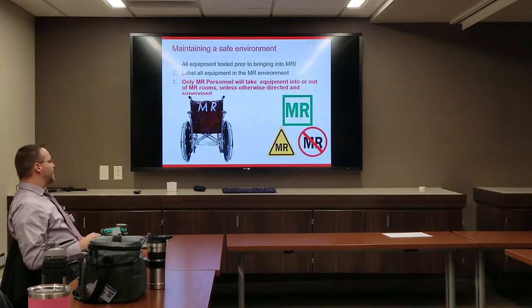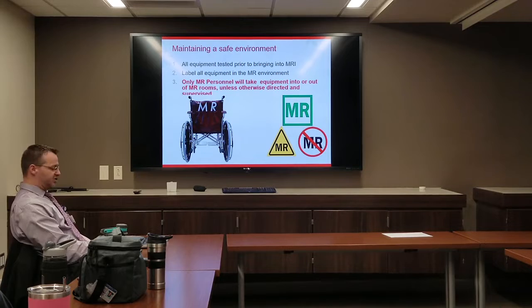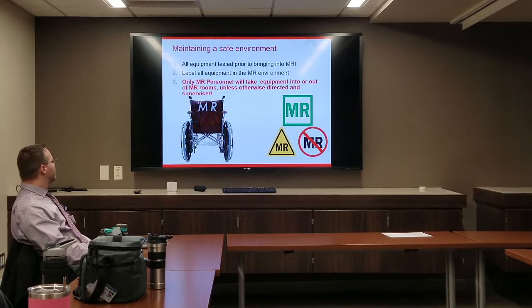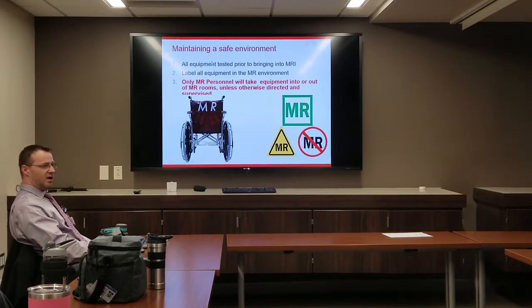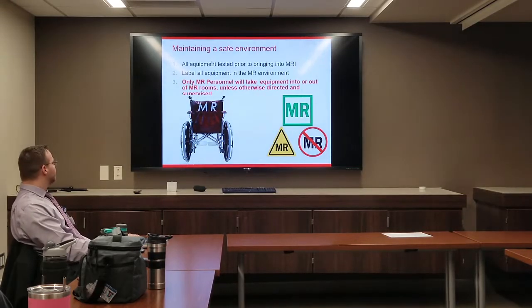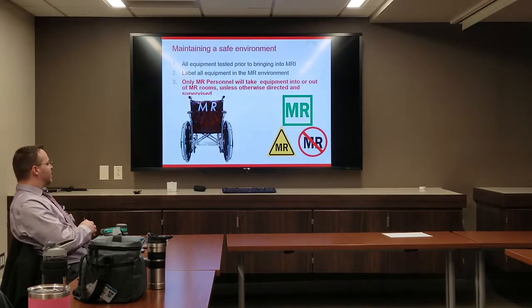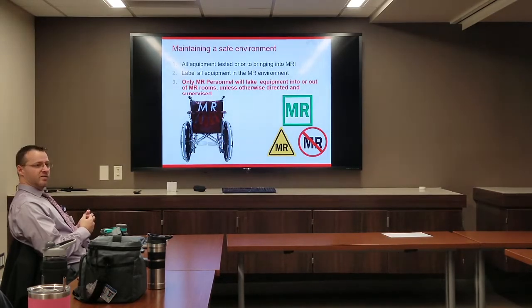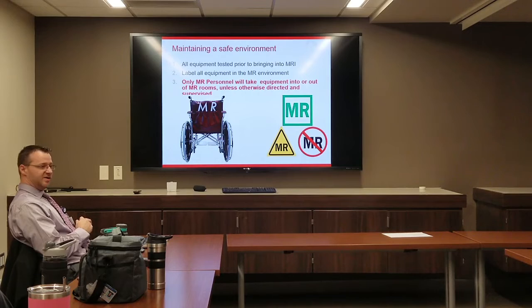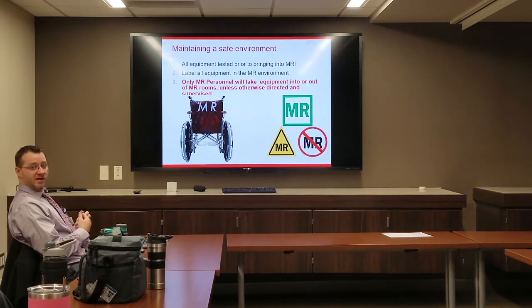All equipment should be tested prior to bringing it into MRI. You want to put labels on equipment kept in an MR environment — whether it's safe, conditional, or unsafe. Only MR personnel should be taking any equipment into or out of the room, unless the other person has been specifically directed by the technologist. Unless you tell someone who isn't personnel to bring it in, they shouldn't be bringing anything in there.